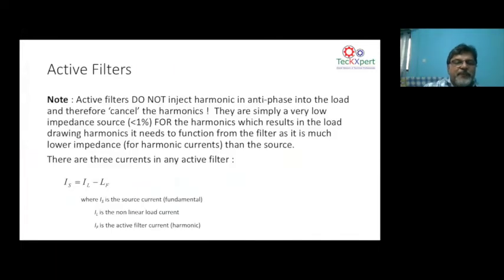Go to the next. What an active filter basically does is, again, very important to know. Sometimes people say active filters just create an anti-harmonic current and inject it into the network. That's a very layman concept, I would say, though widely talked about. Active filters are fundamentally a low source impedance device. When there's a low source impedance device, the active filter produces harmonic currents at a low source impedance. That means you put a VFD load, and the VFD load will see a low source impedance, that is the active filter, instead of taking the harmonic current from a high source impedance, which is the network.